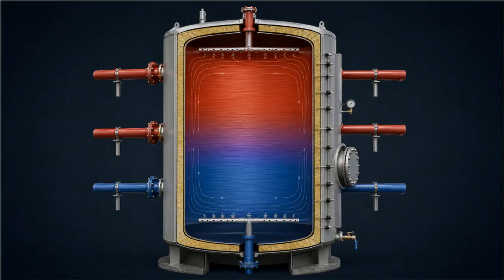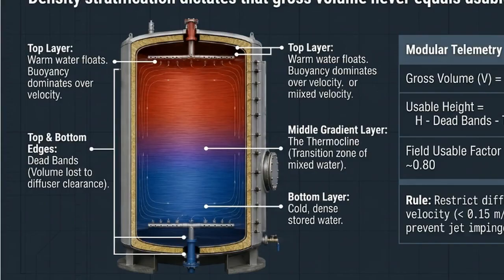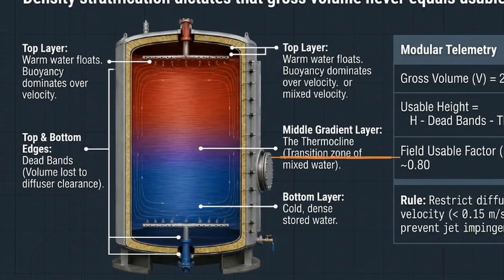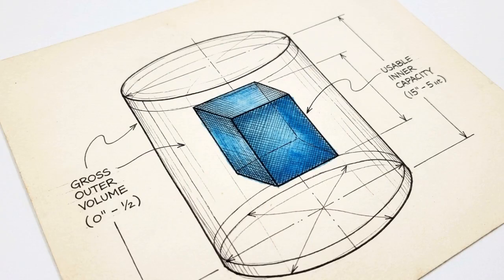Inside the thermal energy storage tank, the entire system relies on fluid density stratification. Warm water floats, and cold water is denser. During a discharge cycle, buoyancy-driven flow allows the densest, coldest water to reliably exit from the bottom. Looking closely at this cross-section, the storage volume is divided into distinct zones. Notice the top and bottom deadbands, which represent volume lost to diffuser clearance, and the central thermocline, the transitional layer of mixed water. Because of these physical realities, the gross volume of the tank never equals the usable volume.